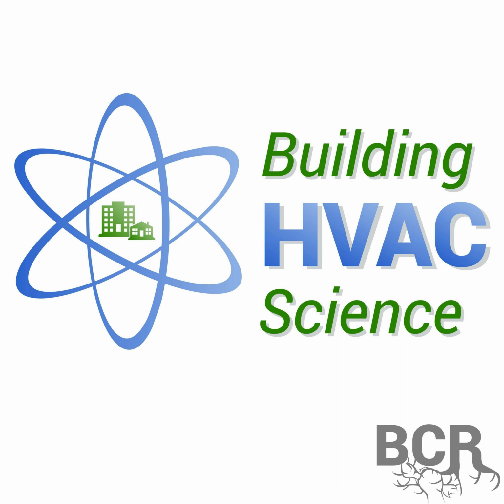As covered before, some of the temperature rise challenges include getting a good value for the input thermal energy, BTUHs, and reading only the temperature of the air and nothing else. That means you have to be out of the line of sight of any other hot surfaces. You don't want to pick up that radiant energy. You also assure that no air is bypassing your measurement and you're measuring the bulk of air, all the air that's moving through the system.